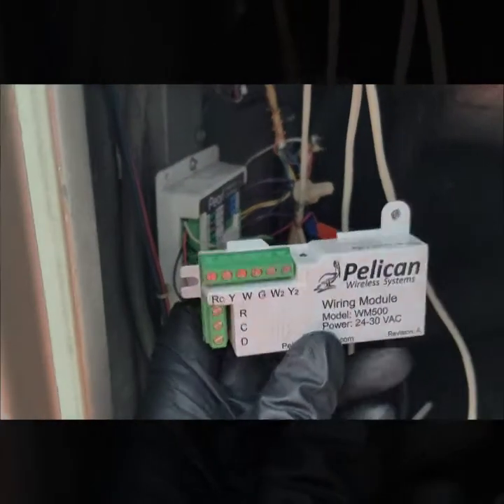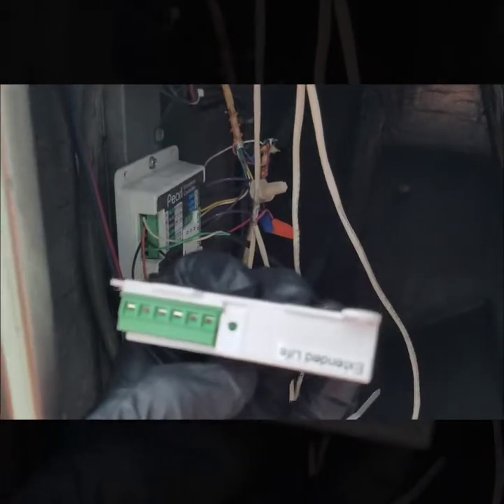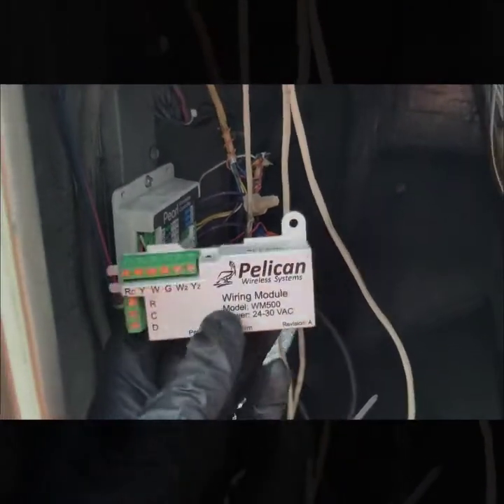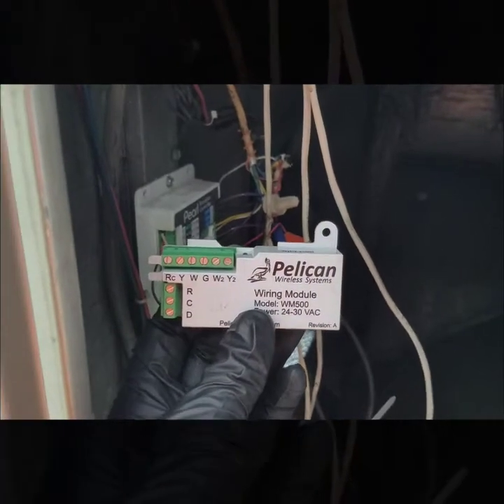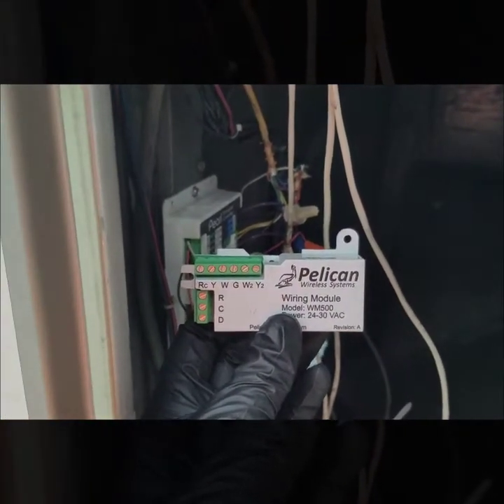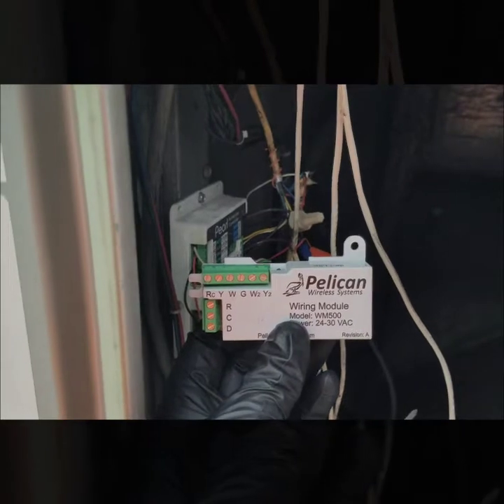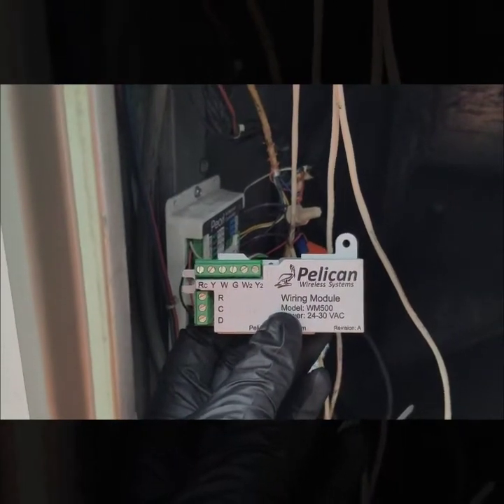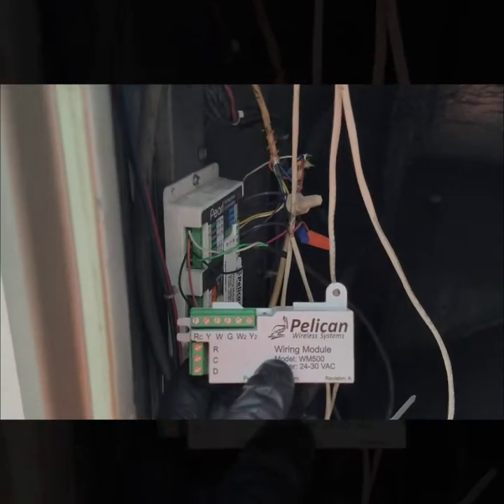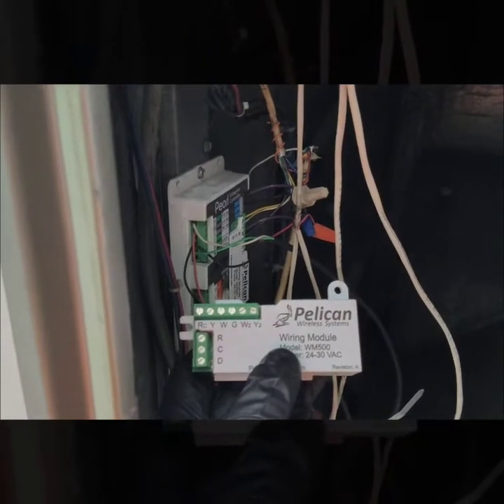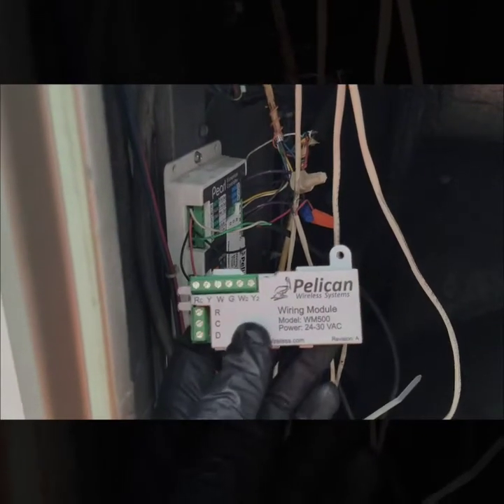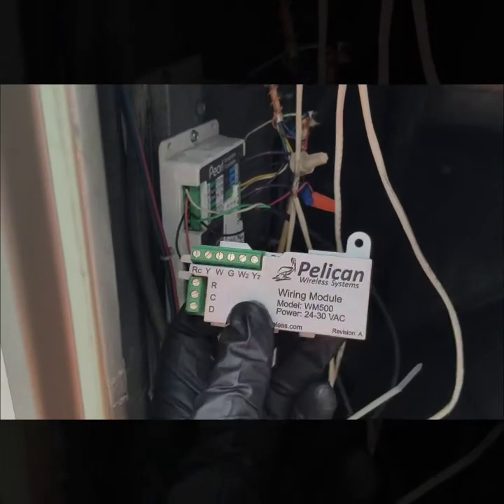But they do have a resolution. These little relay packs, they have ones that are called extended life. They're just built a little bit beefier. The contacts and everything like that are a little bit better. And honestly at this point they might even have a newer fix. But this is what we've been told a couple years ago and we've still been going with it. We've been putting these extended life relays in and it's been taking care of the issue.